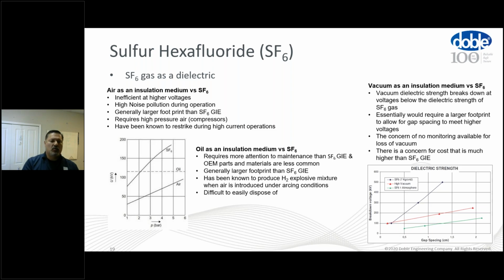So a little bit more on its capabilities as a dielectric. SF6, being what it is, doesn't take as big a footprint as if you would have to use oil or air. If you remember from the slides earlier, the one large oil circuit breaker pictured from the Smithsonian is a very large piece of equipment at over 200 kV. If there was an SF6 breaker in place, which most likely now there is, it's not going to be as big. If it was air, like the air circuit breakers I showed you, it also takes up a large footprint, and it requires air compressors. You need to maintain that air quality and that air pressure very high.